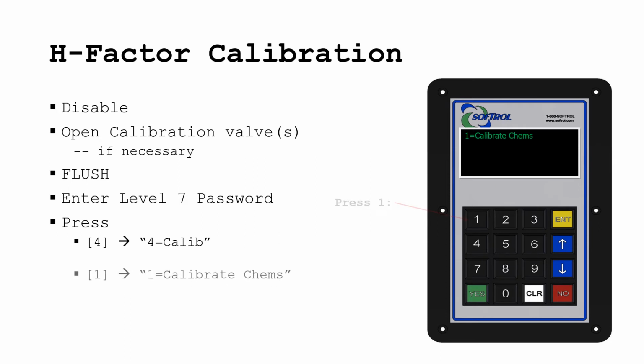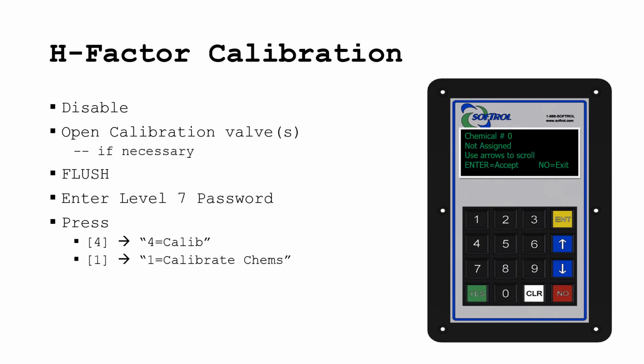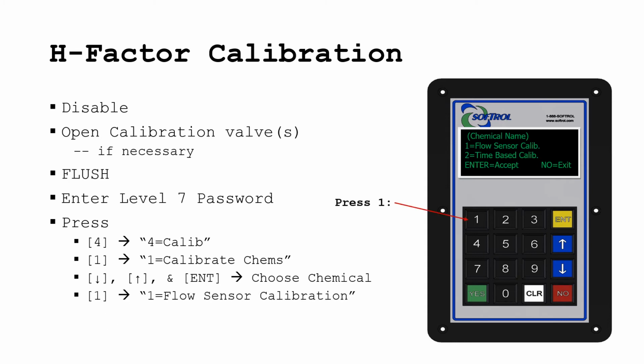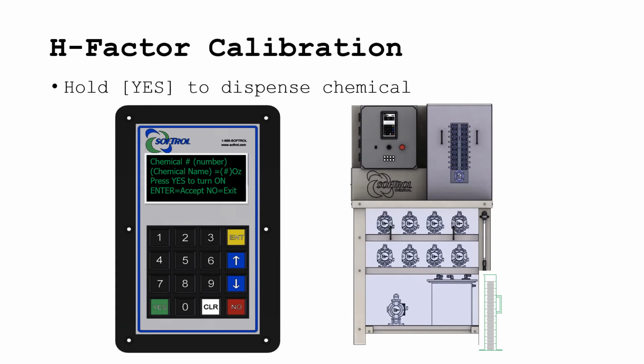Press the 1 key for 1 equals calibrate chems, and use the arrow keys to scroll to desired chemical and then press the ENT key to choose that chemical. Then, you press the 1 key for 1 equals flow sensor calibrations. Next, hold the yes key down briefly, depending on the flow rate, to dispense the chemical. The injection size should be less than 200 milliliters.